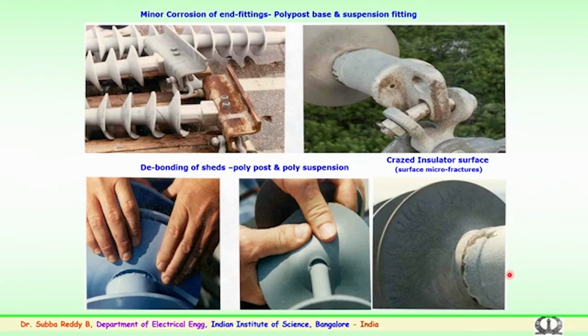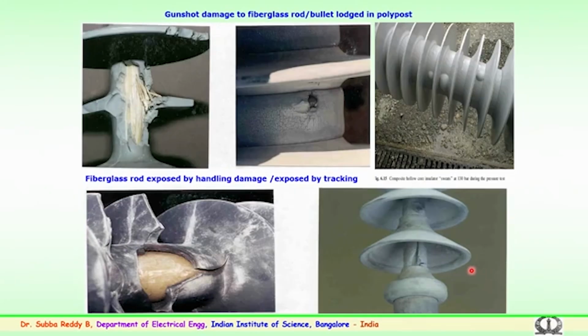Earlier, the sheds used to be made differently, where they were fixed on the surface of the polymer rod. Such gaps or cracks will lead to the failure of the insulator in the field. These are some of the defects exposed because of the damage which has happened. You can see the brittle fracture of the rod. This is likely due to a gunshot or the failure has happened.